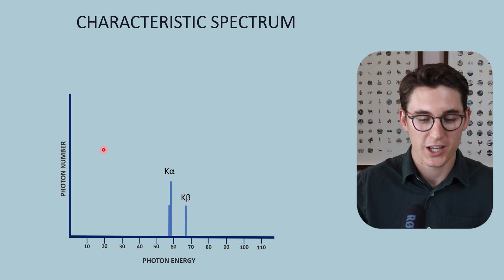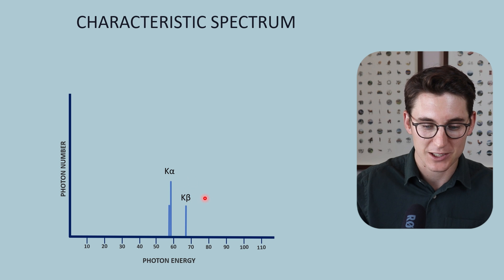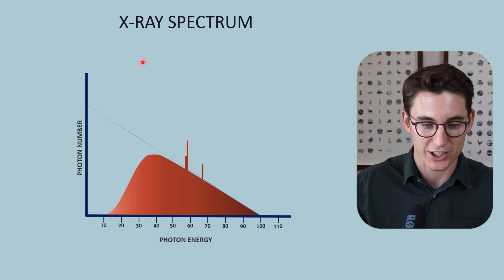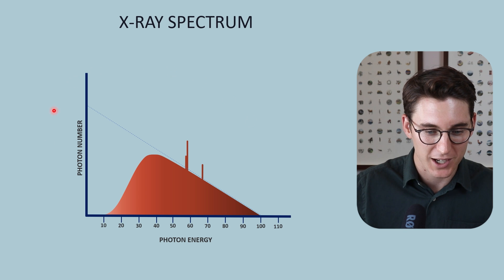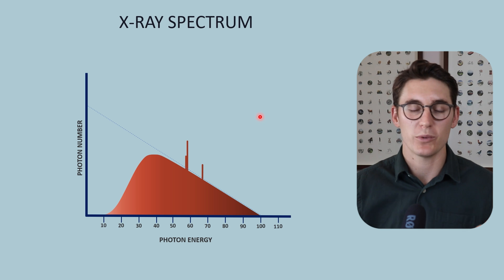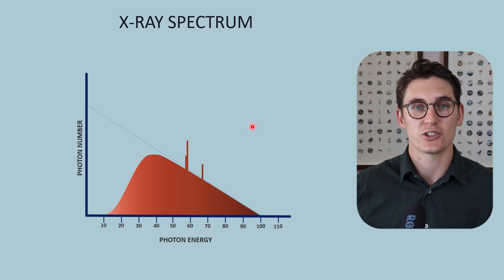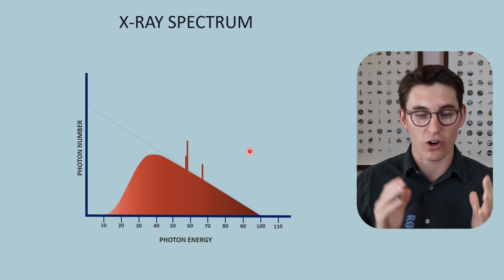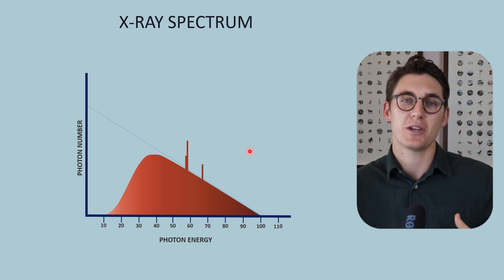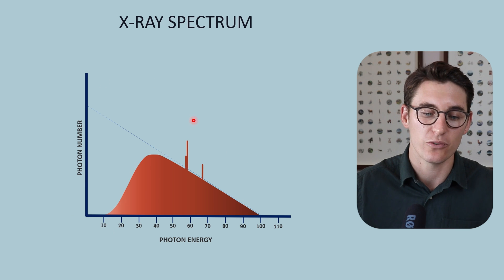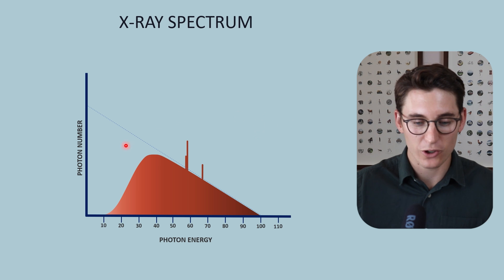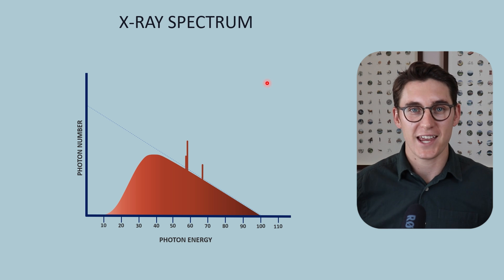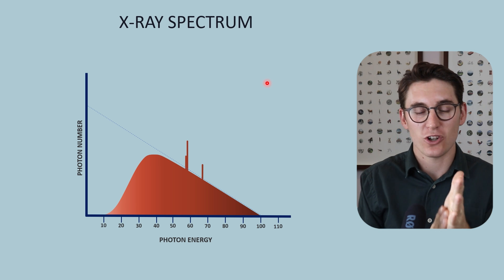Looking again at this graph front on, we can see our k-alpha and k-beta peaks, specific for a tungsten atom. If we combine these with our Bremsstrahlung radiation curve, this is what's known as our x-ray spectrum. There are two things we look at when examining this spectrum: x-ray beam quality — the average energy of this x-ray spectrum — and x-ray beam quantity — the number of photons, or the area under the curve. It's important to note that this is a spectrum with multiple different energies; an x-ray spectrum is not monoenergetic.